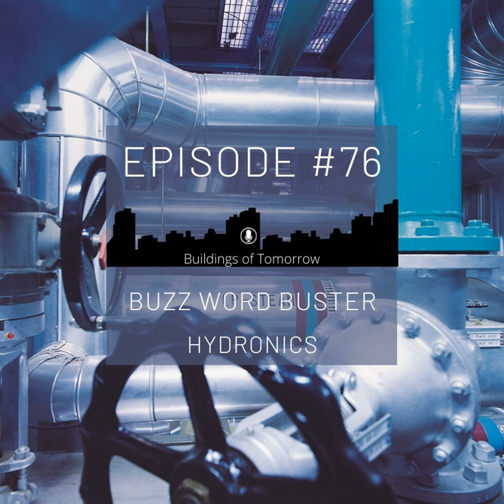The mixing valve, the three-port valve, still has its applications with the traditional mixing circuits. There, it still makes a lot of sense in typical heating applications, where you have your distribution and your consumer circuits in the boiler room, in the heating plant room. There they are still applicable, and they are also energy efficient under these considerations.